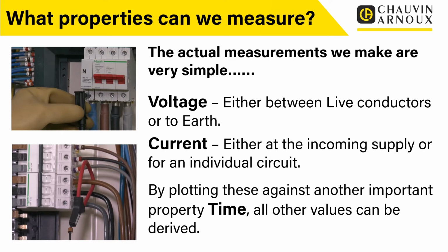So actually, the test connections, when we talk about power quality, are very simple. We're making a voltage connection, as you can see on the top left there, and at the bottom, generally when we take a current measurement, we're using an indirect method, using a Rogowski coil or a current clamp. So we're not even running the current through the test instrument, we're using a clamp to do that. So we make the test connections. Obviously, these things are plotted against time, and then using some very clever test techniques and some very clever maths within the instruments, from those we then get all of the things like power factor and harmonics that we will talk about later on. So when you're concentrating on power quality, don't worry about the complexity of all these measurements, because actually the measurements are just voltage and current, and it's as simple as that.